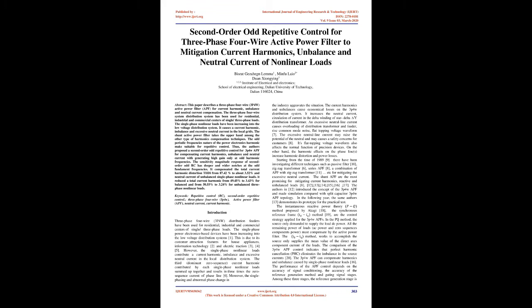It reduced the total current harmonic distortion THDi from 87.42% to about 3.52% and compensated the neutral current of unbalanced single-phase nonlinear loads. It reduced the total current harmonic from 49.45% to 3.43% for balanced and from 50.55% to 3.24% for unbalanced 3-phase nonlinear loads. Keywords: repetitive control, RC, second-order repetitive control, 3-phase 4-wire, 3P4W, active power filter, APF, neutral current, current harmonic.